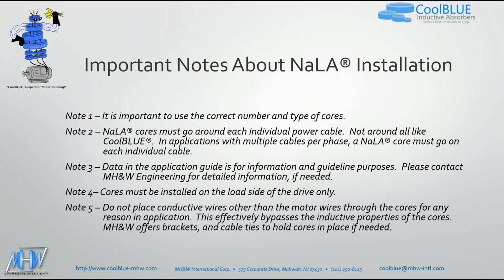The NALA installations are basically just as straightforward as with the CoolBLUE. Again, it's important to use the correct number and type of cores per the application guide. The NALA cores go around each individual power cable. The data in the application guide is for your information and guideline purposes. You can contact MH&W or DREISILKER for detailed information if you need it. Again, they're installed on the load side of the drive only, and they would be installed after the CoolBLUE. And again, you don't place conductive wires other than the motor wires through the cores, including, like I said, the wire ties with the metal inside the plastic.